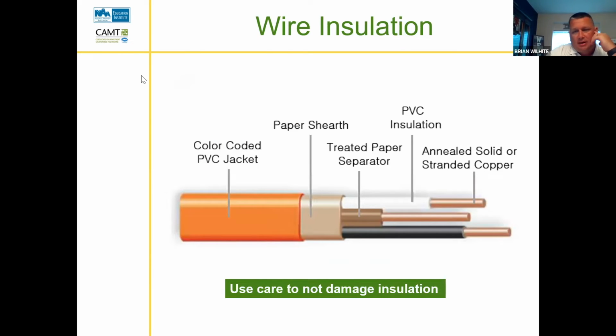This is solid core wire, but they come solid core or stranded. We have PVC insulation or wire insulation on them. Treated paper is our separator and our sheath. And I remember our tools, we had that cable gripper. That's what that does, is it rips the sheathing off these and allows the copper wire to be shown so we can hook them up.